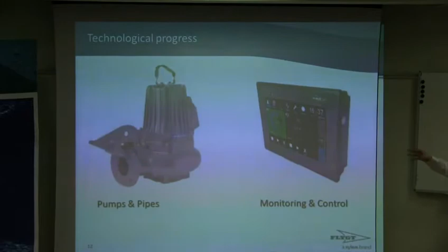On the other side, look at the controllers and the control philosophy of pump stations. 18 years before, you had a pump station with the most modern N pump and probably the most modern controller. Nowadays, in 2016, it's still the N pump, but the control panel looks totally different. So we do things now, as state of the art in electronics, that we couldn't dream of 18 years before. That's the big difference - the pump and pipe side moves slowly, but monitoring and control is totally different.